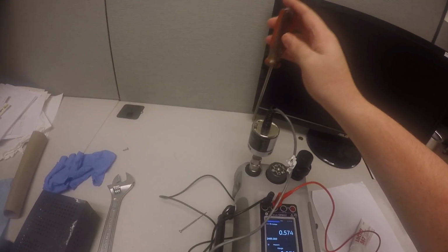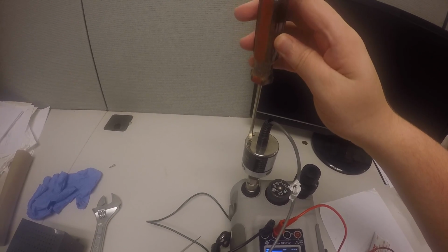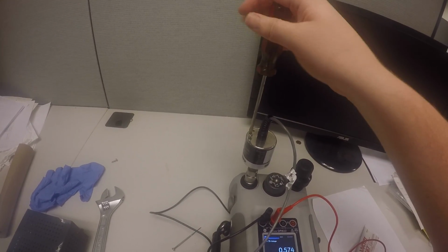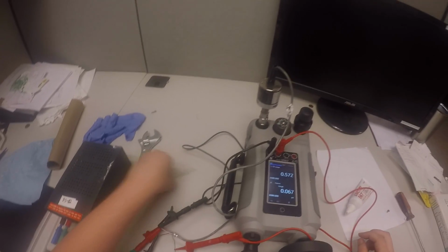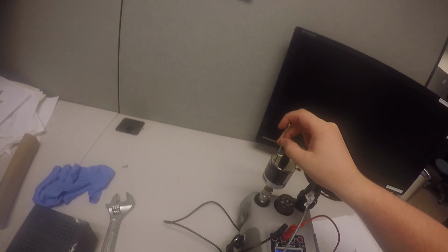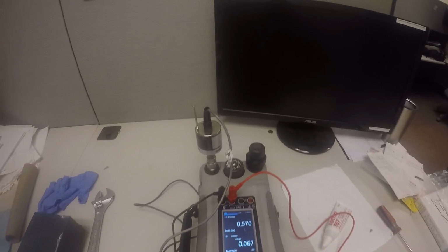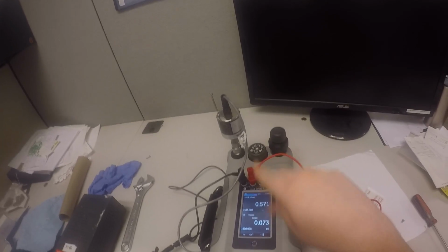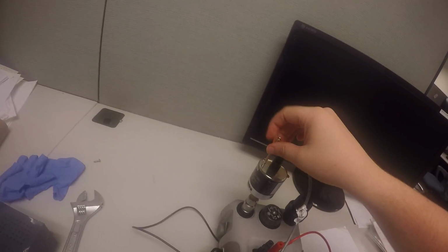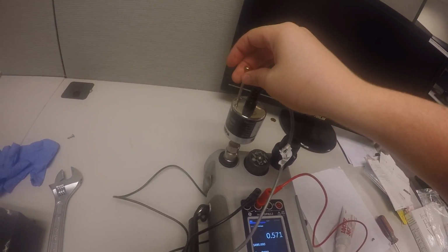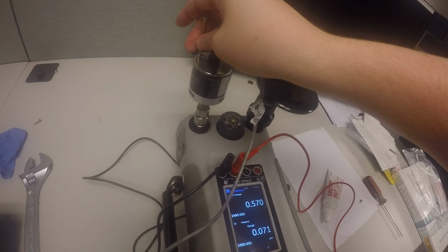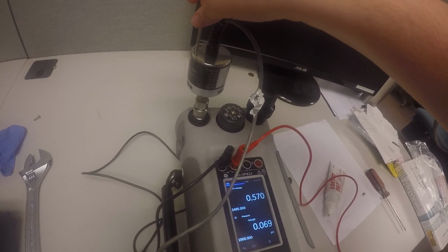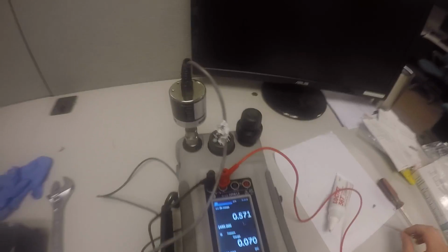So next we're going to use our screwdriver to take off these small screws on top of the transducer. So we're going to unscrew that real quick and just take it out with hand. Alright, and now we're going to use this small screwdriver right here. Now you kind of just want to go into these little holes that opened up from the screws and find there's very tiny screws inside that you need to turn. And once you turn these, you can adjust the voltage output from the transducer, which will adjust the PSI measurement. So these can be a little bit hard to find, so just get in there and try to run around for them. And I can't seem to find it this time, so we're going to skip that section.